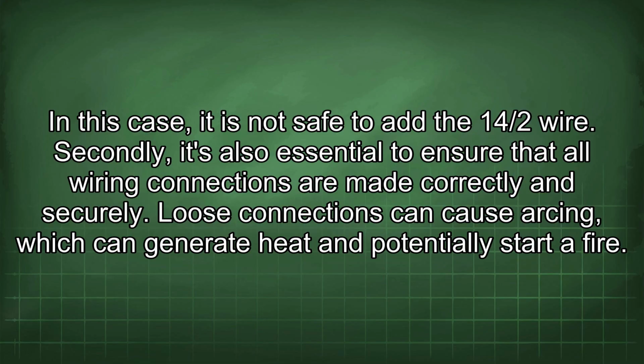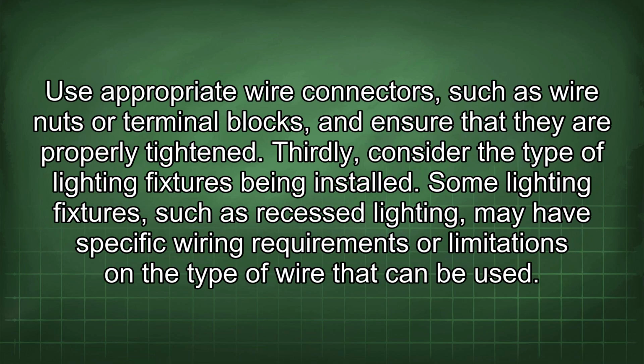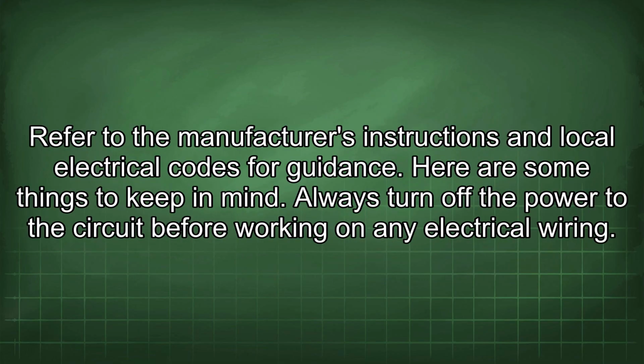Secondly, it's also essential to ensure that all wiring connections are made correctly and securely. Loose connections can cause arcing, which can generate heat and potentially start a fire. Use appropriate wire connectors, such as wire nuts or terminal blocks, and ensure that they are properly tightened. Thirdly, consider the type of lighting fixtures being installed. Some lighting fixtures, such as recessed lighting, may have specific wiring requirements or limitations on the type of wire that can be used. Refer to the manufacturer's instructions and local electrical codes for guidance.